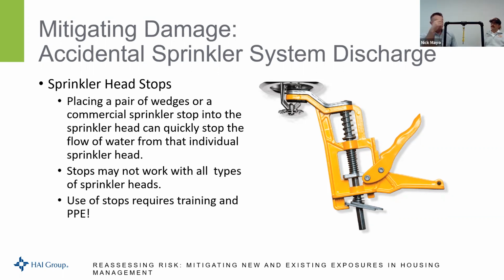Now, doing it here in this controlled environment, it is extremely easy to operate this device. If water was flowing from this, and let's say it's 10 feet up in the air, and now I'm on a ladder working off a ladder, you will be drenched and soaked in water. It is a little more difficult. And not clean water. Potentially that water could be dirty from sitting in the pipes and corroding the pipes and things of that nature. So use of sprinkler stops like this requires training and personal protective equipment. Certain stops may work with one type of sprinkler head, and another type of sprinkler head may require a different type of stop. That's why in the fire service, we tend to just carry a pair of chocks or a pair of wooden wedges, because it seems like usually this works for us the majority of the time.